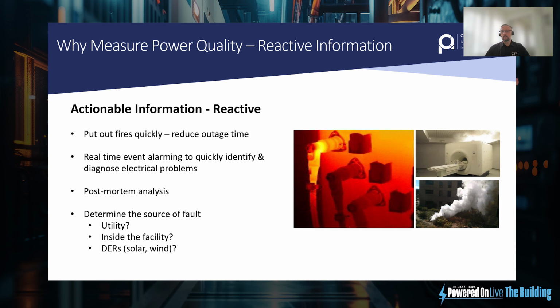Problems that can occur are overheating, as I mentioned, premature equipment failure. There's loads of things that can happen. If you're not monitoring, which we found in many cases, not just in the EV world, when an event occurs, and I assure you an event will occur at some point, you lose the ability to break that down and do root cause analysis. And it might be that you determine, oh okay, there was nothing we could do. It was a really bad situation. Something happened from the grid or something else happened and we understand what happened. And you don't spend weeks and months arguing and fighting and trying to investigate a problem, because you've got the actual facts in front of you of what occurred at that point in time.